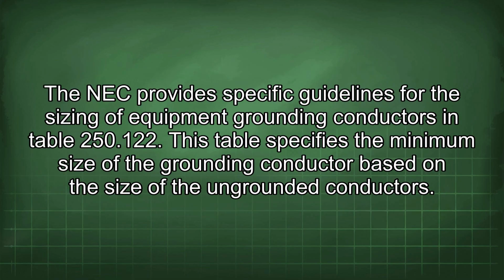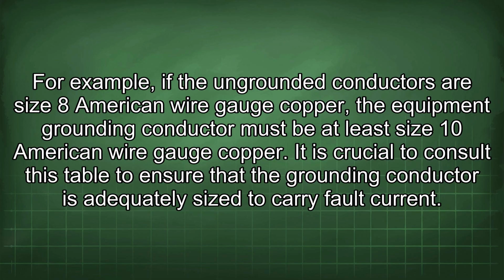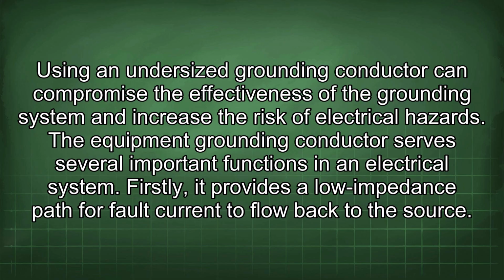The NEC provides specific guidelines for the sizing of equipment grounding conductors in Table 250.122. This table specifies the minimum size of the grounding conductor based on the size of the ungrounded conductors. For example, if the ungrounded conductors are size 8 American wire gauge copper, the equipment grounding conductor must be at least size 10 American wire gauge copper. It is crucial to consult this table to ensure that the grounding conductor is adequately sized to carry fault current. Using an undersized grounding conductor can compromise the effectiveness of the grounding system and increase the risk of electrical hazards.